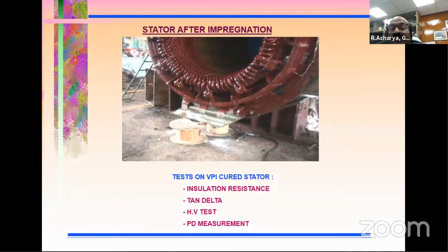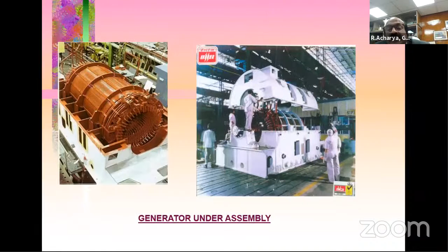That's the basic system. And then of course, after that, a lot of quality checks are made: insulation resistance, tan delta, high voltage test, and PD measurement. You can see here the job under assembly. After that, the job is placed inside, and then the top cover is placed to complete the winding, and then it forms an assembled stator, and of course it goes for a complete performance test.